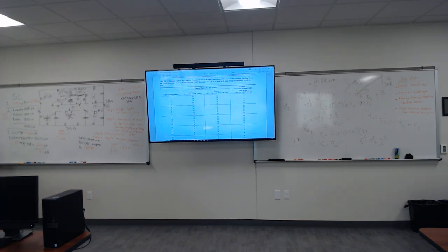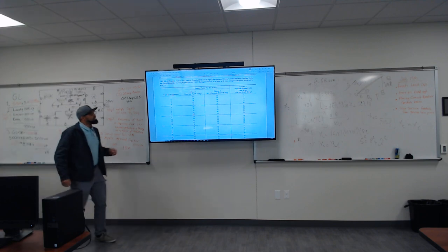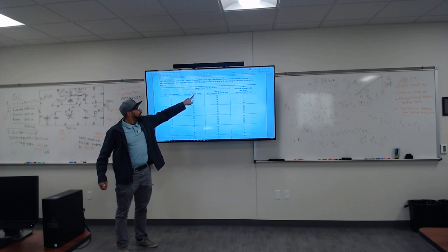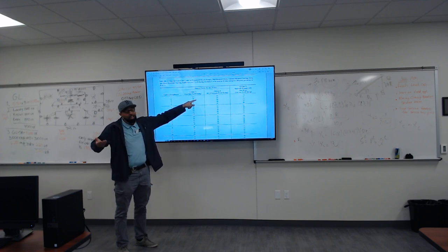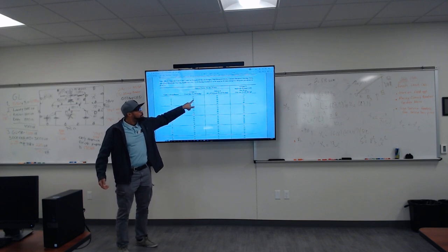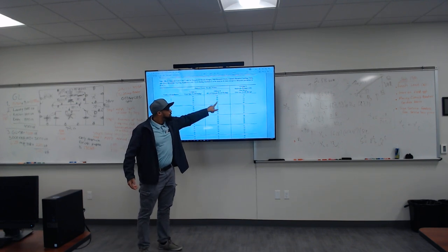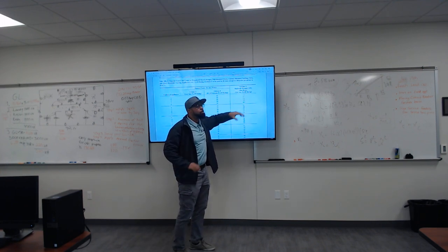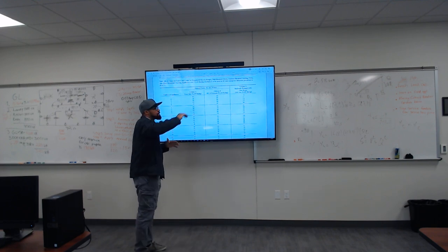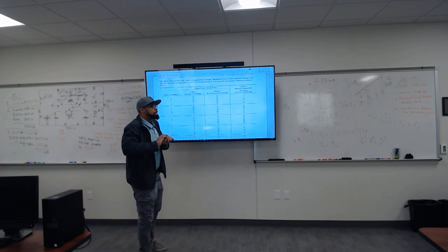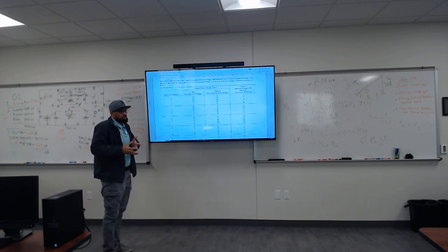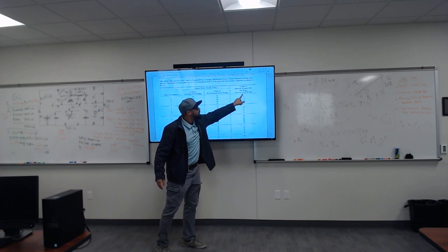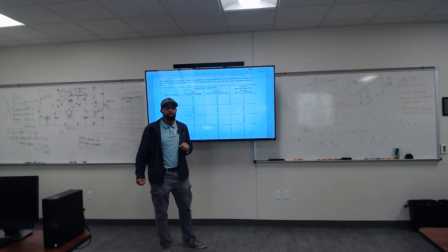All right, so our oven, whatever it is, are we gonna use column A? It says less than 3.5 kilowatts. Ours is what, 10.5 kW? Are we going to use column A? No. Are we going to use column B? No. Okay, column C. All right, not over 12 kW. So we're not over that threshold of 12 kilowatt. So since we're not, and we have 10.5 kW, what are we going to say for calculation purposes? 8 kW. All right, put that down.